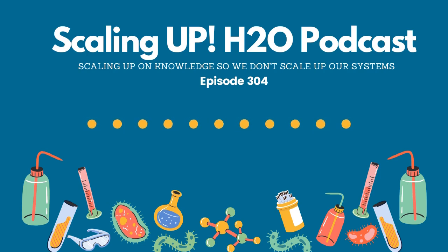Now, a lot of people ask me, do I prefer corrosion coupons or do I prefer the electronic corrosion coupon monitors? And of course, the more data sets that you get, the better it is, but those are expensive. And the only name I can think of is Corrater. That's a name brand, and the actual systems itself have a generic name. And I'm sure I'm going to get a bunch of calls and write-ins because I can't think of it right now. But whatever that is, every so many seconds, it takes a reading and calculates that into mils per year. So you can see hundreds, if not thousands, of data sets over a day's time. So a lot of times those could be overkill in a system that's working well.